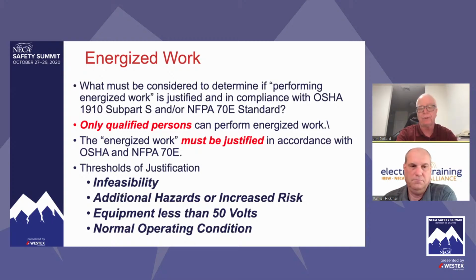Additional hazards or increased risk, as Palmer pointed out, is where we can't de-energize this equipment because it creates a greater hazard. Maybe if I de-energize this panel board, I shut down purge fans and I'm going to allow a combustible atmosphere to develop somewhere else. That's an additional hazard. But for you, the contractor, you have to understand that when you use that justification threshold, additional hazards or increased risk, it's a double-edged sword, okay? Because now the equipment that the owner is telling you they can't do without for 20 minutes might be out for 2 days or 2 weeks if something goes wrong. So you need to document that.